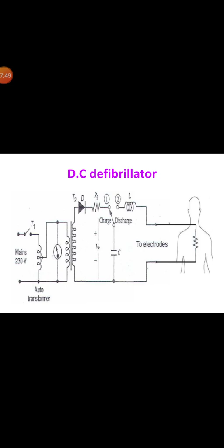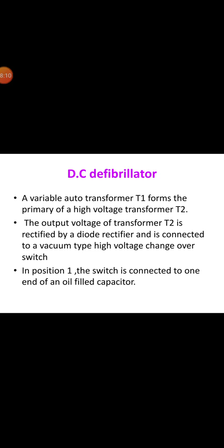A variable autotransformer T1 forms the primary of the high voltage transformer T2, and the output voltage of the transformer T2 is rectified by a diode rectifier and connected to a vacuum tube high voltage changeover switch. In position 1, the switch is connected to one end of an oil filled capacitor. In this position, the capacitor charges to the voltage set by the positioning of the autotransformer.